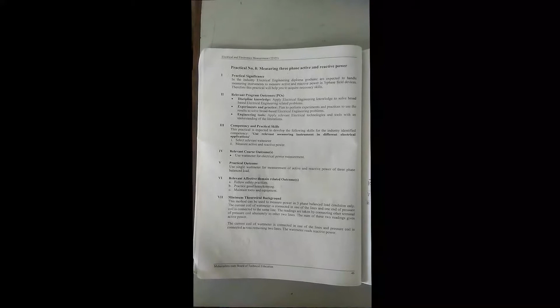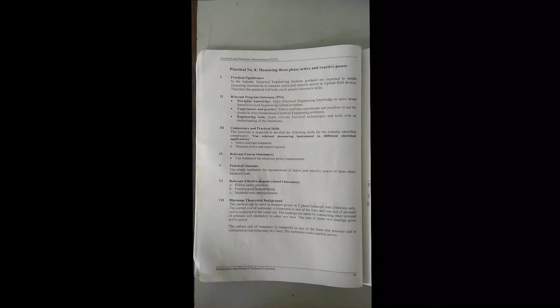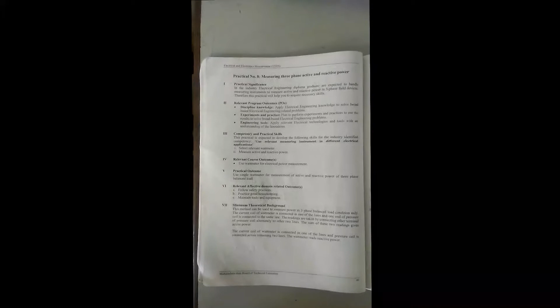Next, minimum theoretical background. This method can be used to measure power in a three-phase balanced load condition only. The current coil of the wattmeter is connected in one of the lines and one end of the pressure coil is connected to the same line. The readings are taken by connecting the other terminal of the pressure coil alternately to the other two lines. The sum of these two readings gives active power. For reactive power, the current coil of the wattmeter is connected in one of the lines and the pressure coil is connected across the remaining two lines. The wattmeter reads reactive power.